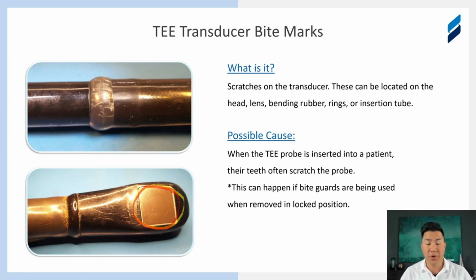This can cause some really severe failures in the future. The little RTV here that I'm going to circle on the left hand side, the edges of that can start to get chunked out and then expose the next patient to fluid intrusion. Right, so there's an electrical shock safety issue, and then number two, imagine it's sitting inside of the sterilization fluid for 20 or 30 minutes. It will actually get in there and begin corroding the crystal itself.